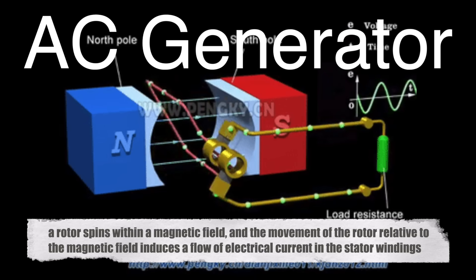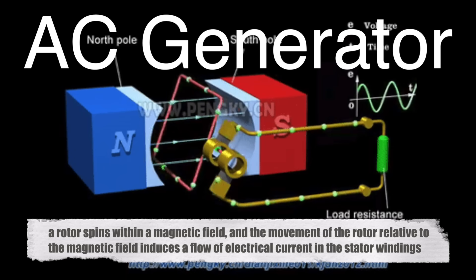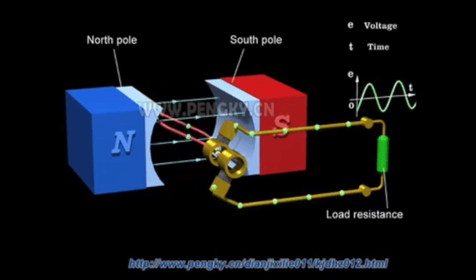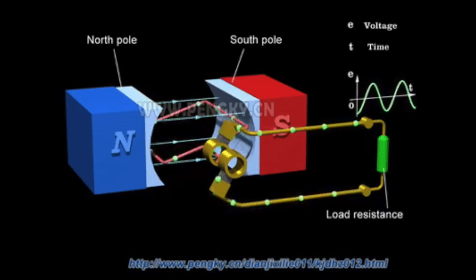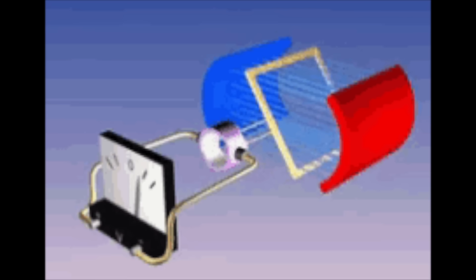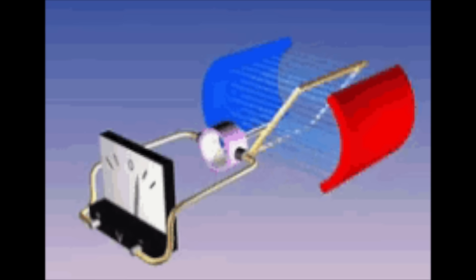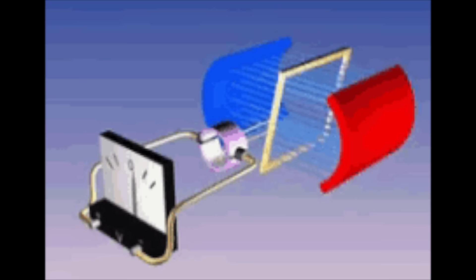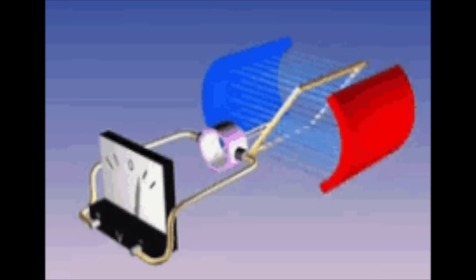In a typical AC generator, a rotor spins within a magnetic field, and the movement of the rotor relative to the magnetic field induces a flow of electrical current in the stator windings. The frequency of the AC produced is directly related to the speed of the rotor's rotation, which is why maintaining a consistent speed is critical in applications where frequency needs to be stable, such as in power generation for the electrical grid.